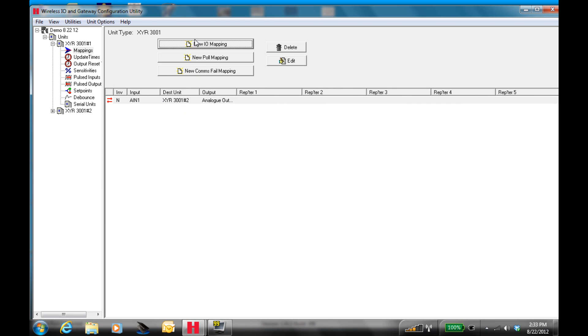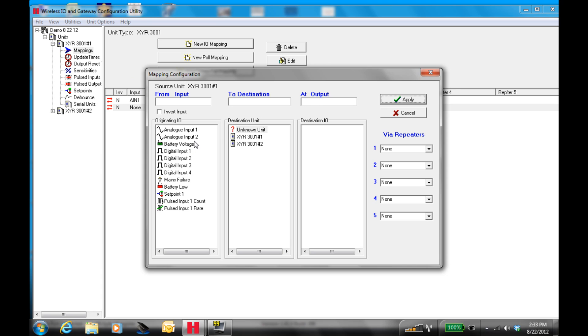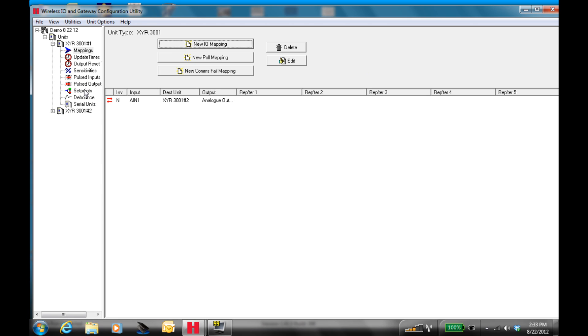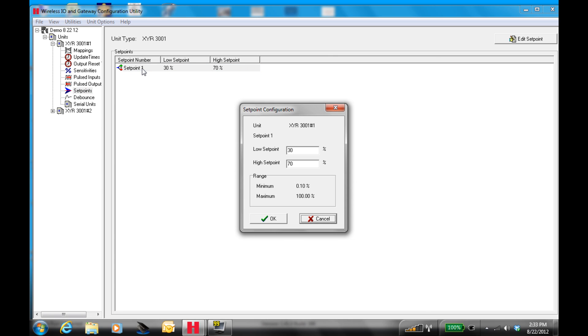The first step of your mapping is done. You can continue with this with discrete inputs and outputs, battery low, and battery voltage. You can also have set points, which are values given for analog inputs that range outside of your set point values. You can set those set point values by going to set points. In this radio, we only have one set point driver and that's set point one. You can adjust the low set point and high set point by double clicking on the set point or hitting edit set point. In this case, our low set point is thirty percent and our high is seventy. You can adjust that anywhere from one to ninety nine.